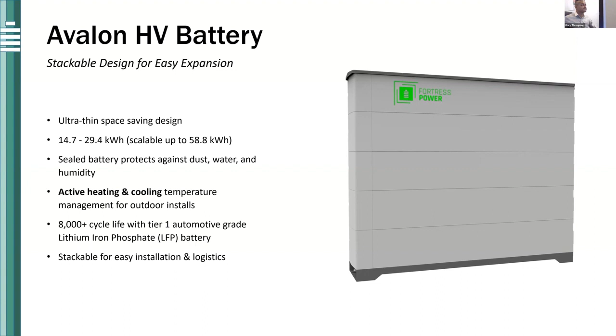What's really great about the high voltage system is that it's an indoor or outdoor solution. The video alluded to a built-in heating system in the battery unit, which makes it able to be installed outdoors without having to worry about low temperatures as much as you would with a 48 volt battery. Warranty on this is similar to the 48 volt Fortress units: an 8,000 cycle life warranty or 10 years, whichever comes first.